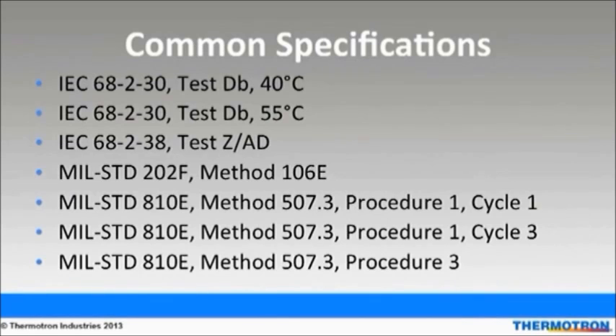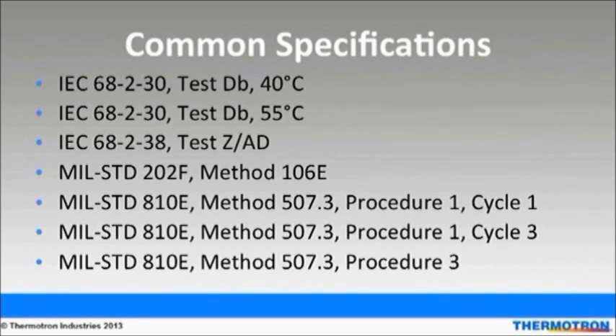Many products go through standard testing procedures that are widely accepted, including those from the military, IEC, UL, and IEST. Thermotron's 8800 Programmer Controller includes 10 pre-programmed tests including four MIL-STD and three IEC profiles as shown on the slide.